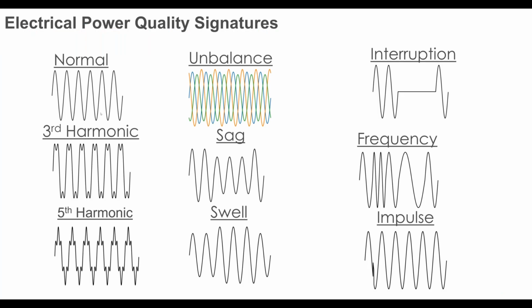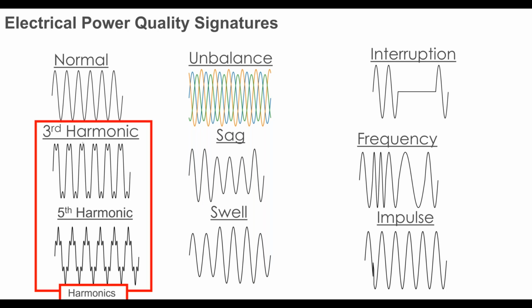What are power quality signatures? Well, for good power quality delivered to end-use appliances, it's essentially a sine wave, and the frequency is uniform. It looks something like this normal one here. Now, one example of bad power quality is when we have increased harmonics in the sine wave. What is a harmonic? Essentially a multiple of the base frequency, being 60 hertz. The third harmonic will be around 180 hertz, and the fifth harmonic will be around 300 hertz. So the point here is that the wave is no longer a pure sine wave. You see these fuzzy lines in the peak and the valley. What exactly do customers see when harmonics are introduced into the power quality? You will have increased heating and less efficient use of energy. So that's the impact to our customers.